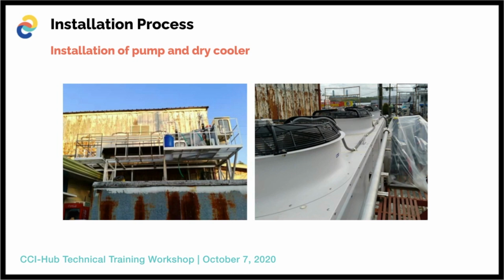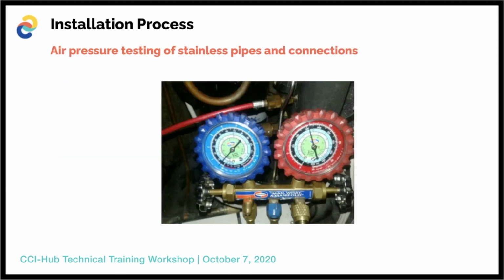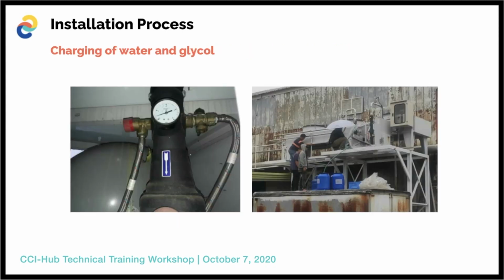Air pressure testing of stainless pipes and connections. By doing this procedure, we'll make sure that there will be no leaks in the systems. We will be using oxygen-free dry nitrogen to double-check all piping connections for possible leakage. And the next one is charging of water and glycol.